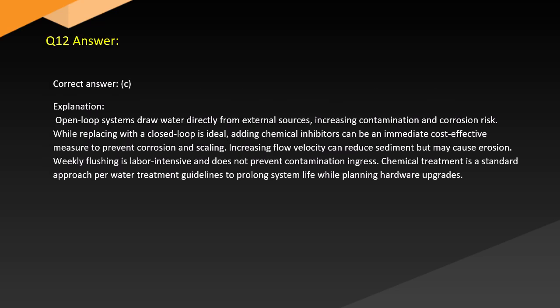Answer. Correct answer: C. Explanation. Open-loop systems draw water directly from external sources, increasing contamination and corrosion risk, while replacing with a closed loop is ideal. Adding chemical inhibitors can be an immediate, cost-effective measure to prevent corrosion and scaling. Increasing flow velocity can reduce sediment but may cause erosion. Weekly flushing is labor-intensive and does not prevent contamination ingress. Chemical treatment is a first-step approach per water treatment guidelines to prolong system life while planning hardware upgrades.